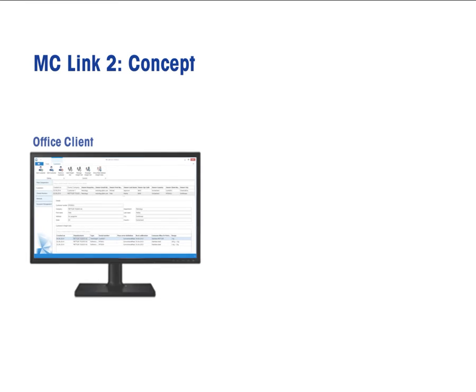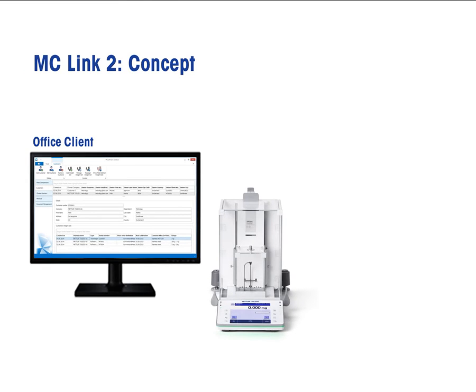The software is built in two sections. With the office client, all administrative tasks are managed. For example, installation of comparators and climate sensors, definition of the weighing process, and uncertainty analysis. Here, we also manage customer data and calibration methods.